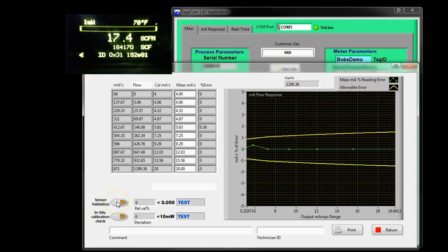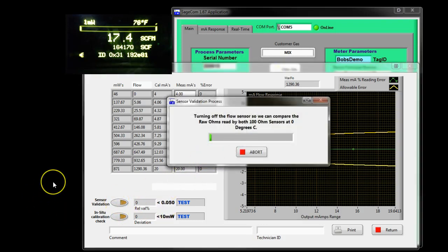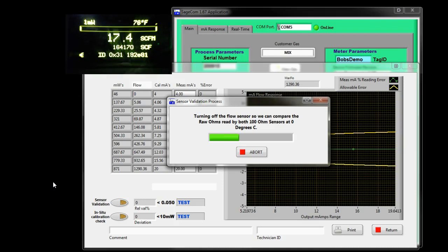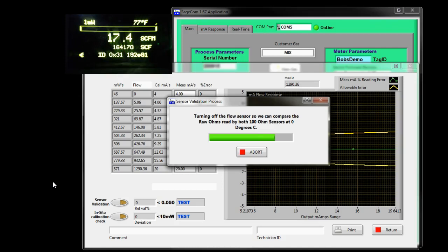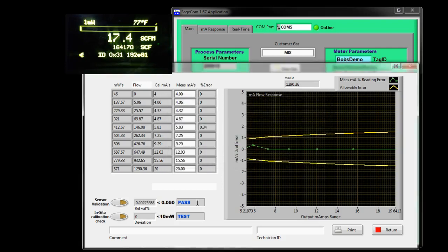The next test is a sensor validation check and it is determining whether the sensor has any internal damage, however rare that would be unless you smash the sensor against a wall or something. It's going to confirm that everything's in good shape because what it's doing is shutting the power off and now both 100 ohm RTDs essentially are thermometers and they're measuring the temperature that your sensor's exposed to. It's going to have to have the same ohms for each of these RTDs and if it does, when you divide one by the other, if they're less than 0.05 relative variance, you're in good shape and the meter will pass. Notice where my cursor is. It always takes about a minute because it's shutting the power off to the meter. Passed.